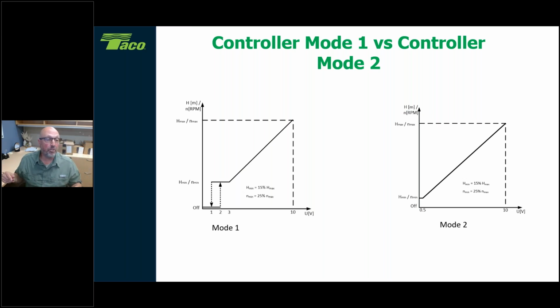So here there's a minimum flow rate that has to go through that heat exchanger in order to extract those BTUs out of the water or out of the flame, right? So that's where you get to that mode 3 volts and say, all right, I don't want to go any slower than this, because otherwise you're going to mess me up in my heat exchanger. All right, my delta T becomes too wide at that point. And you'll get hot spots and whatnot.